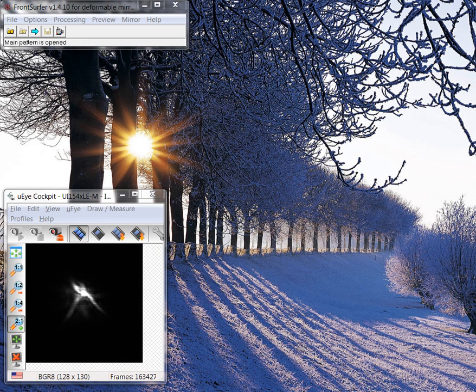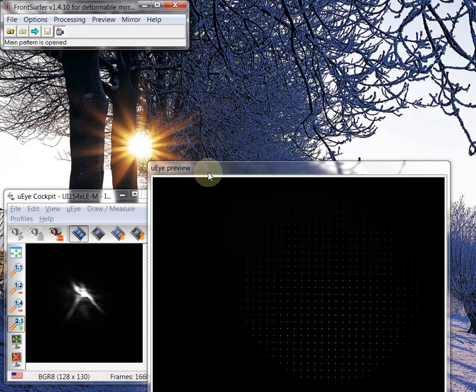In this video I'm going to show how to calibrate and run an adaptive optical system based on a 109 channel piezoelectric mirror. So let's see what we have in our setup. We have an imaging camera. What we see here is a live image from the system, from the imaging camera, and we also have a Shack-Hartmann sensor, which we can run the preview of with this button.